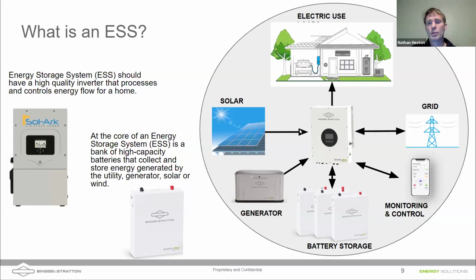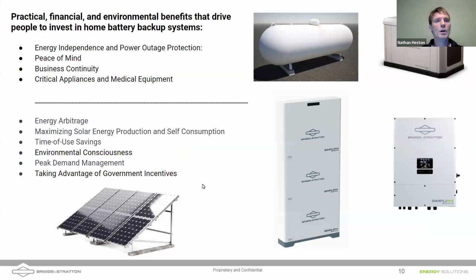An inverter also, the Sol-Ark 15k, as well as our inverter that's shown on the right side of the screen, can control a generator. So as the batteries get low, the inverter has the responsibility of starting up that generator. I'll show you how to program those set points into a Sol-Ark later in this talk. They will use the 2-wire start functionality of our generators, and I have some wiring diagrams and pinouts to show you on that.